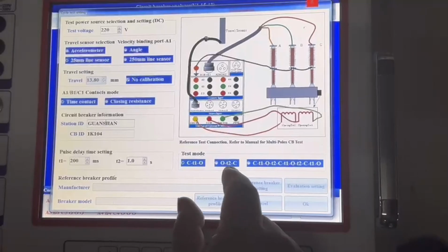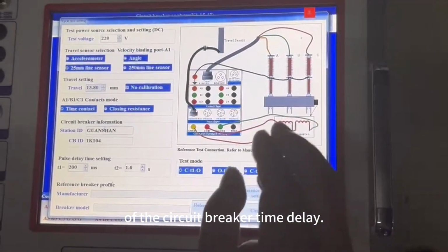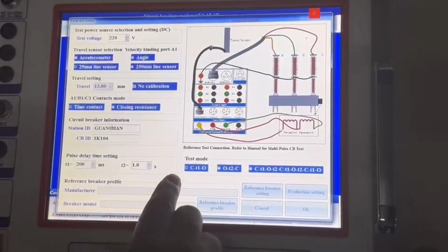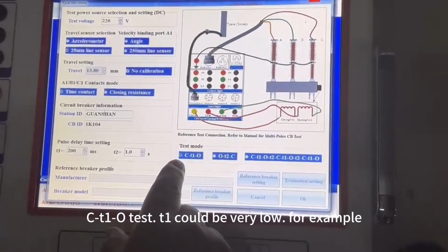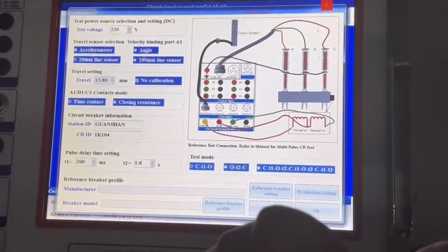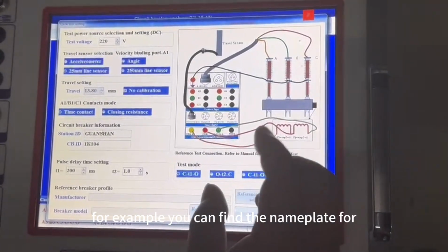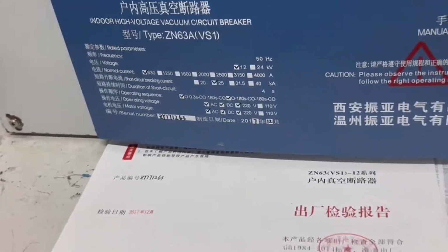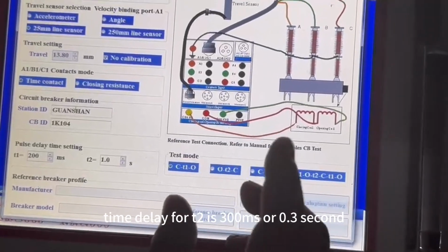T1 and T2 must be more than the minimal requirements of the circuit breaker. The minimal value can be found from the nameplate of the circuit breaker. Normally for C-t1-O test, T1 could be very low. For example, 0 is also okay. But T2 normally has a minimum requirement. For example, you can find on the nameplate for this circuit breaker the rating sequence is O, 0.3 seconds, CO. That means the minimum time delay for T2 is 300 milliseconds or 0.3 seconds.